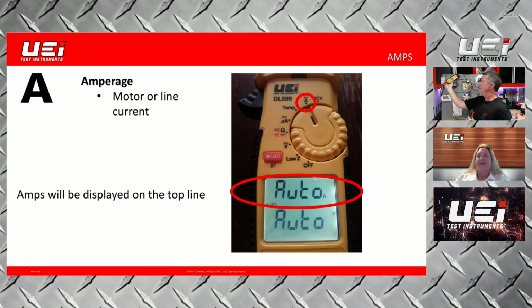So we'll set that one on amp setting. We're going to measure the amp draw on this particular board. This is an entire 80% Goodman furnace, except for the blower, and we'll reduce the blower on it a little bit.